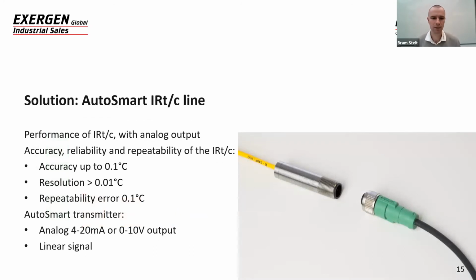This is a product that we launched the end of last year, where we basically combine the performance of the IRTC with the smart conversion of a AutoSmart transmitter. To meet the requirements of the market, of the high accuracy and the high repeatability, we took the performance of the IRTC. So the IRTC in terms of accuracy, repeatability, reliability is very good. It can have an accuracy up to 0.1 degrees C. If you're on the calibration point, it's even 0.01 degrees C. The resolution of the IRTC itself is 0.001, which is the Johnson noise, because it's unpowered, so it has extremely high resolution. The repeatability error is very small, 1/10 of a degree, so this meets the market demands.